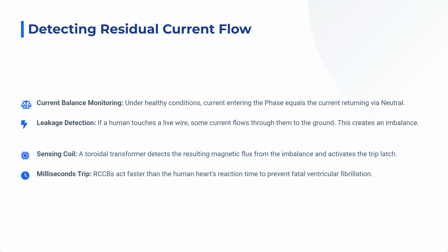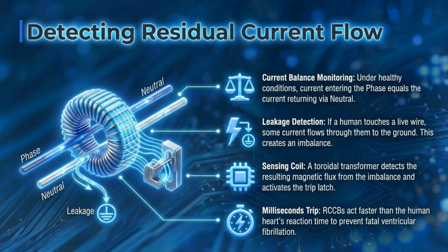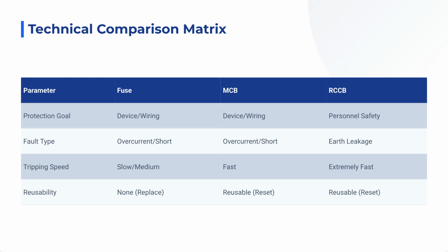Under normal conditions, the phase current equals the neutral current. If leakage occurs, for example, current flowing through a person to the ground, the imbalance is detected by a sensing coil. The resulting magnetic flux activates the trip latch in milliseconds, acting faster than the human heart's reaction time to prevent fatal ventricular fibrillation. This technical comparison matrix summarizes the key differences.